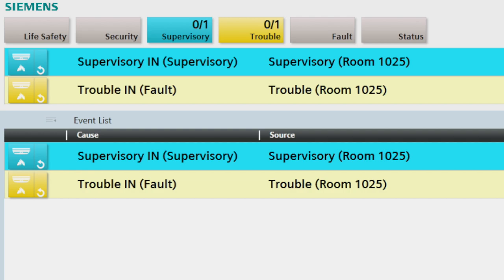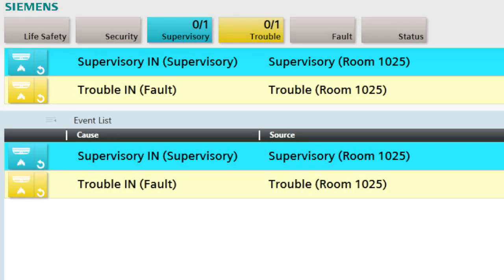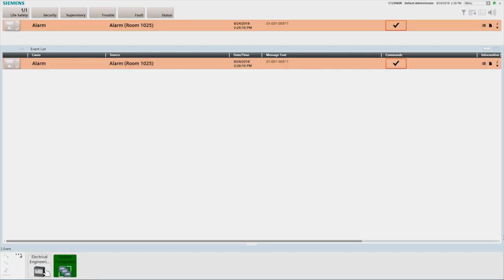This is the standard operator interface. However, additional user interface screens are available for configuration and maintenance of the system. First, we have the summary bar, which is located at the top of the screen. It provides constant system status by displaying a summary of the number of events in the system of each type: life safety, security, supervisory, trouble, fault, and status. When a new event is received, the corresponding event lamp will flash and the event count will increase.